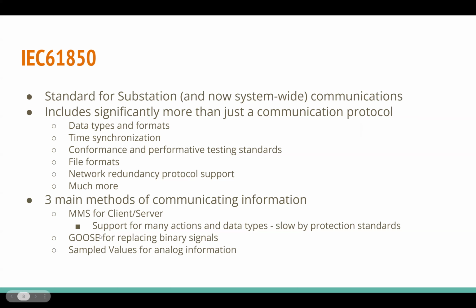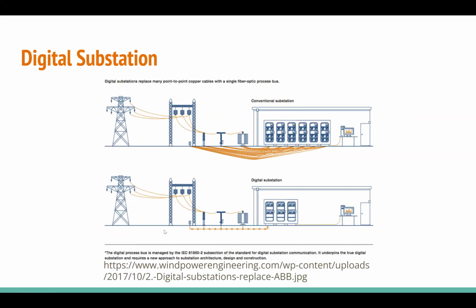These are really the two big things that make 61850 what it is, and that's what you would be sending on this cable right here. This underground cable is that single communication cable that would carry GOOSE and sampled value messages. The GOOSE messages would come out and tell a breaker to open, or would come from the breaker telling its status. And the sampled value streams would come from the current transformer and the voltage transformer to show what the current waveform looks like for those electrical values.